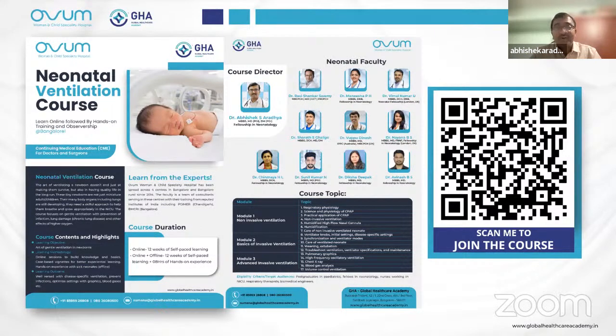There's a question on reuse, ETO or autoclave. I think it's a very difficult question to answer. But all this is optimization. Suppose you have used the circuit for 4 hours or 12 hours for a baby and the circuit is good. Before that, you should know the principles of ETO. ETO will not work if it's a wet circuit. It has to become dry. The circuit has to be clean and dry before you go for ETO. Cleaning is a mandatory thing. You can't use the same circuit for every baby. You will transmit infections. So if you follow all the rules, maybe you may use it for 1 or 2 babies and then prevent reuse.